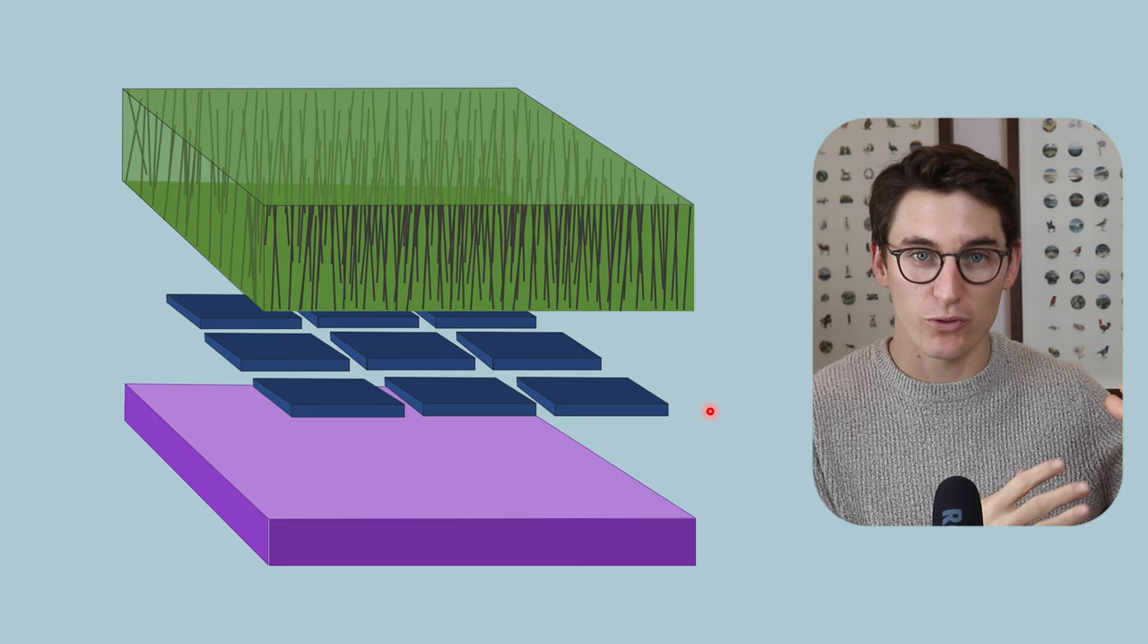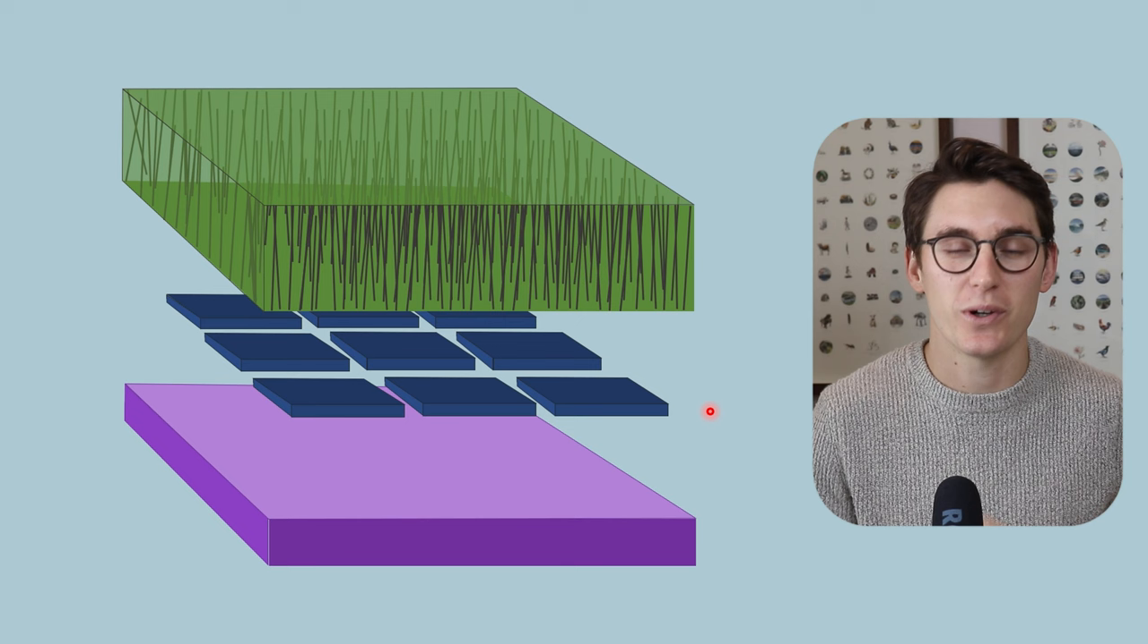We are releasing electrons down onto the third layer here, which is our thin film transistor array. Now this photodiode is made up of hydrogenated amorphous silicon. Hydrogenated amorphous silicon is a semiconductor that converts light into electrons. We are converting light photon signal into an electron signal. Those electrons then head towards our thin film transistor array.